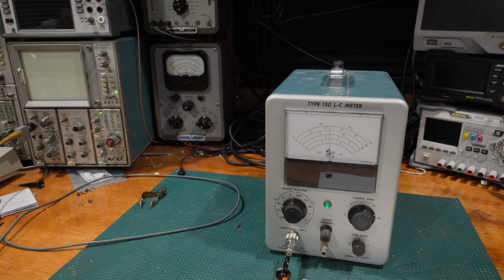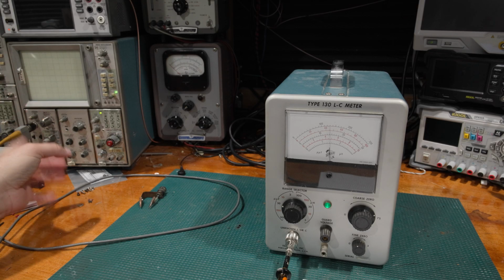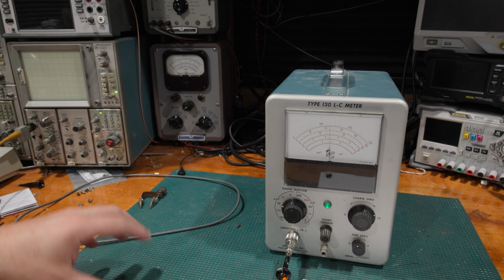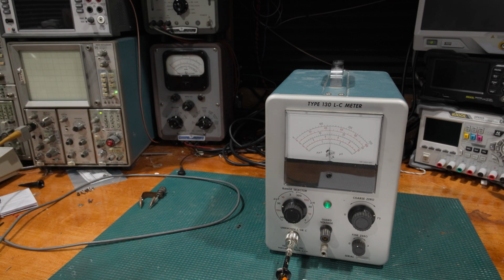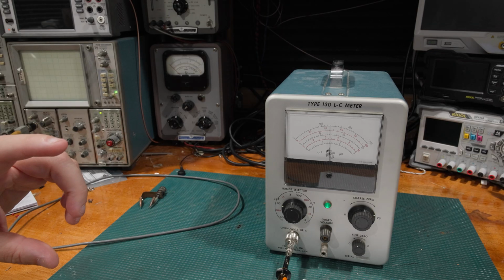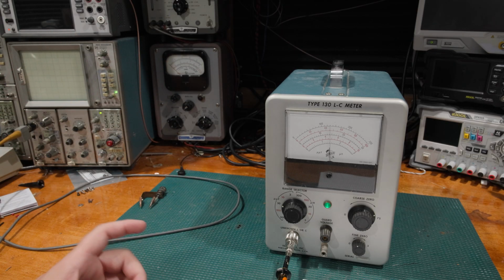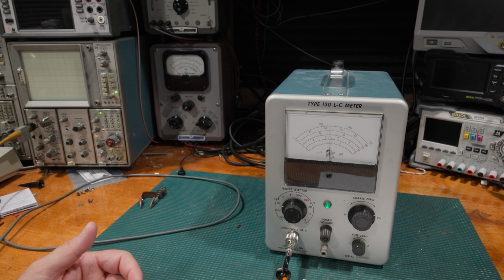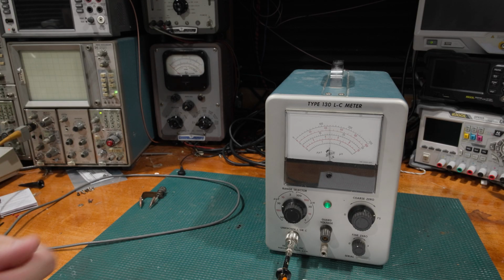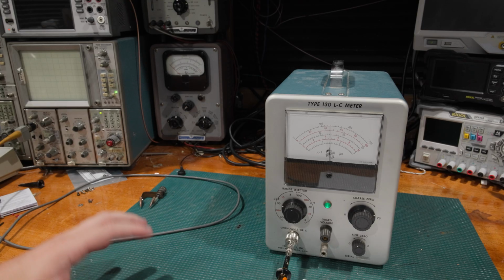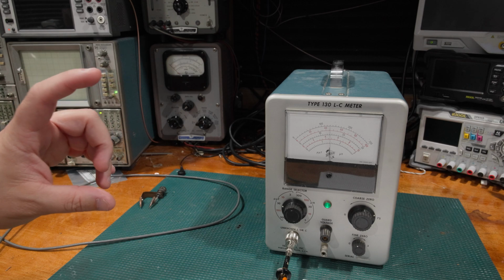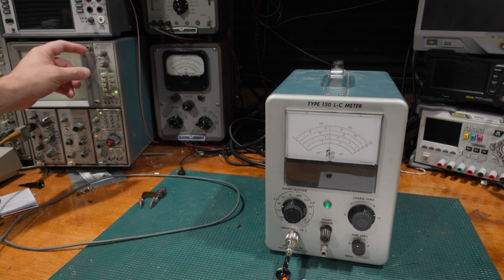So the other thing, too, is on a 400 series scope, if we're doing the calibration on a 7000 series amplifier, it wasn't called out as much, but a 400 series scope, the upper channel, is it the bottom channel or the upper channel? One of the channels is set in such a way to make sure the same probes will work for both. So there was kind of a compromise of the adjustment with making sure the probes could be used on both inputs. You can set it, and the adjustment range was so wide on the front end of a 400 series scope that you could set it perfectly, but then the probe may not compensate on the bottom because there is a range.